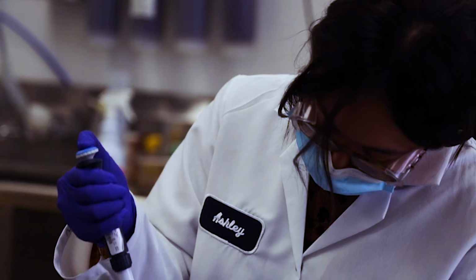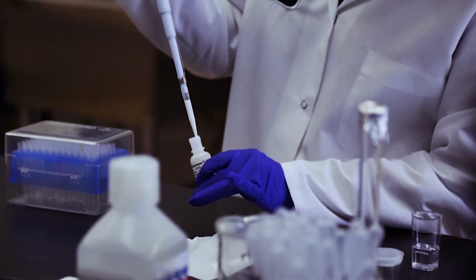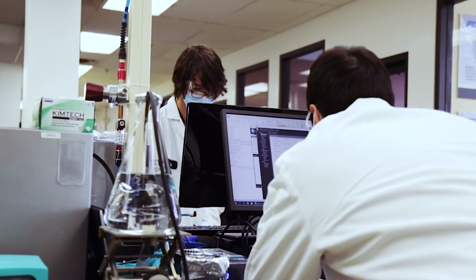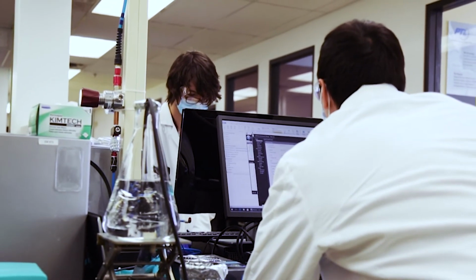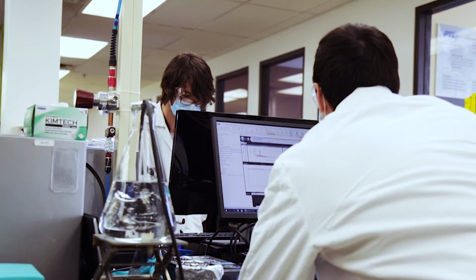Of primary focus in the validation, if you could pin it to a focal point, it would be repeatability. From there, you have other characteristics. You have ruggedness, where you can take how repeatable the procedure is, but with varying slight elements such as a different testing day, a different chemist, a different instrument, that sort of thing. So that collectively defines precision.